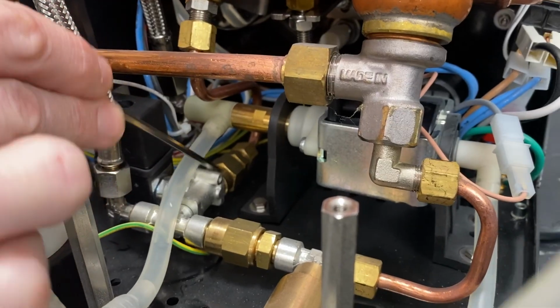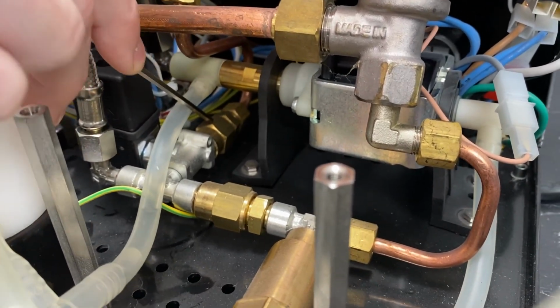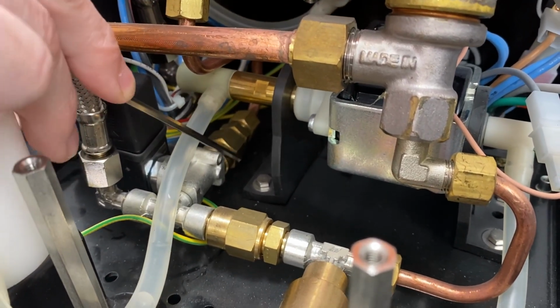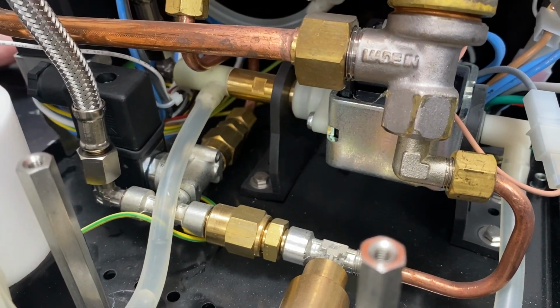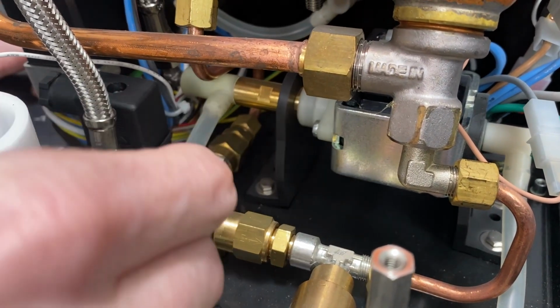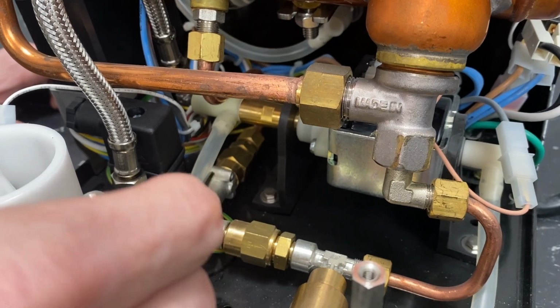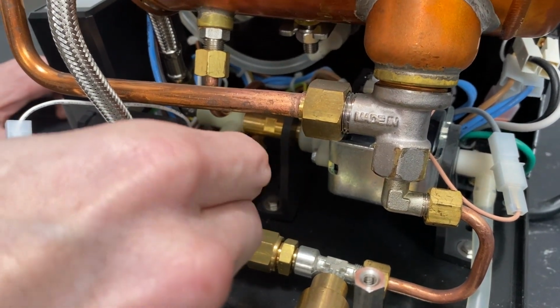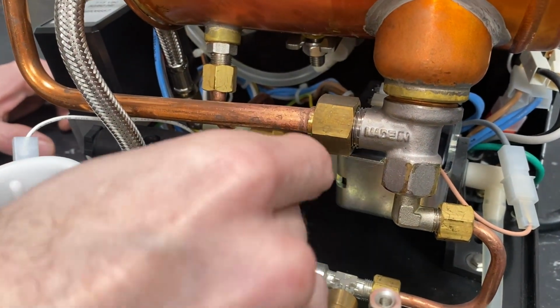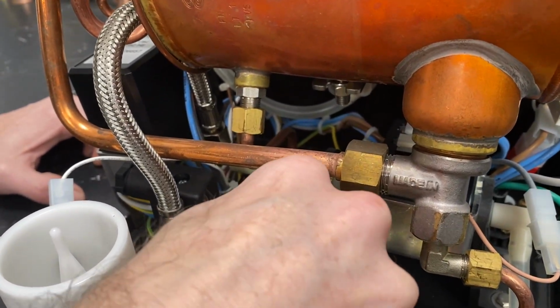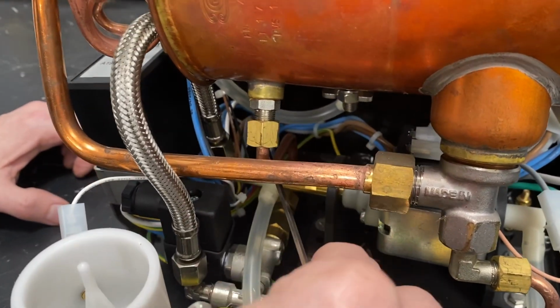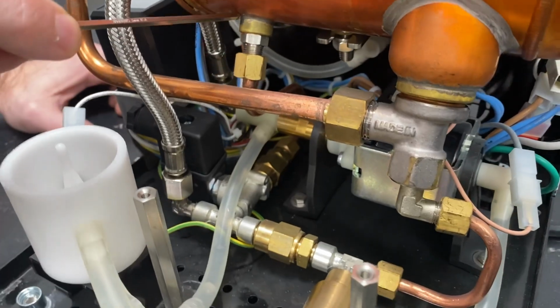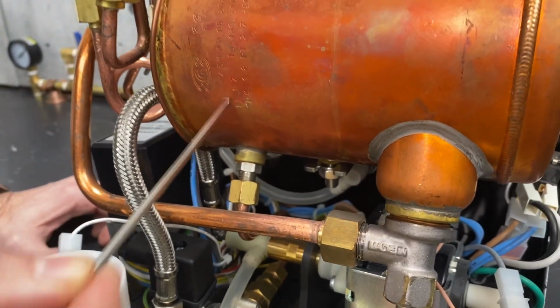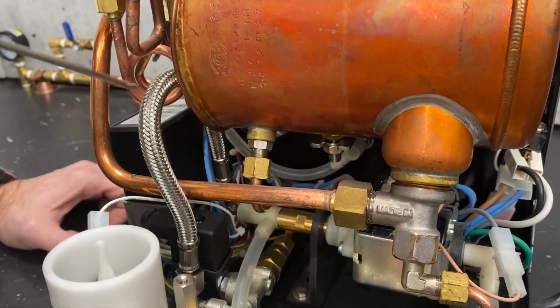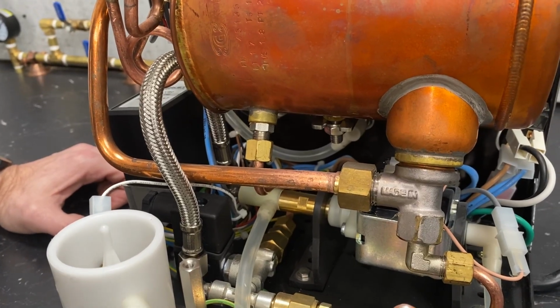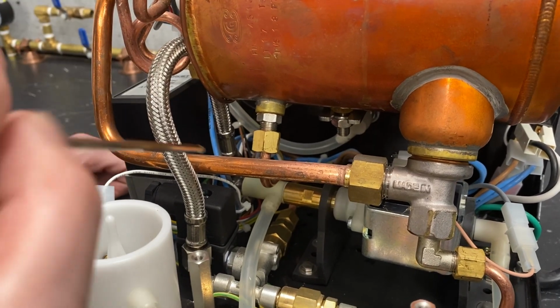After the solenoid, a common trend with these is there's a non-return valve right after it. Non-return valve, water goes one way but not the other. So if you ever have some water sneaking back into this solenoid here, you have an issue right there. Off the non-return valve, you're going to come up to this copper line right here that goes into the boiler and fills the boiler up. Okay, I'll give you a little bit more detail on how all that magic occurs once we get to the top of the boiler.